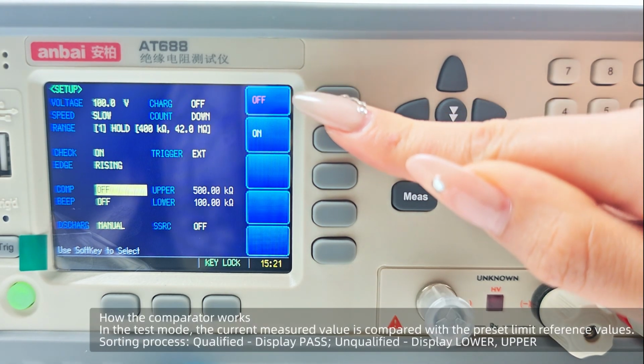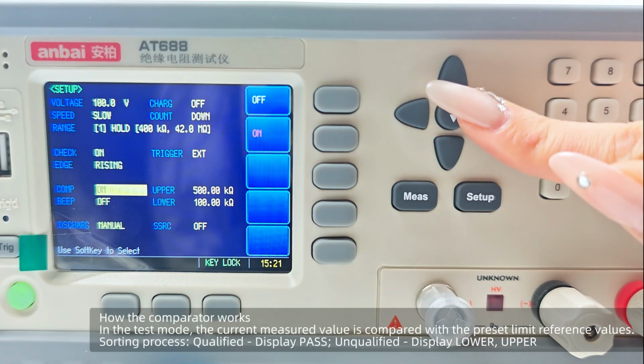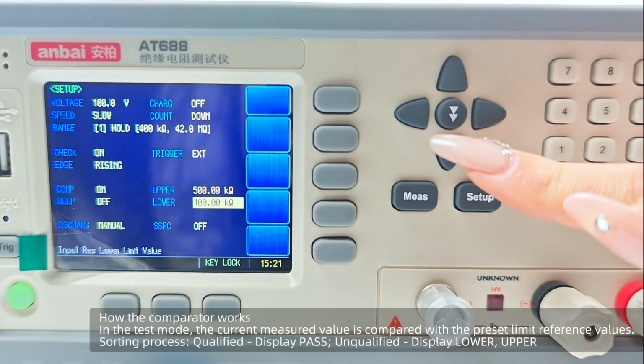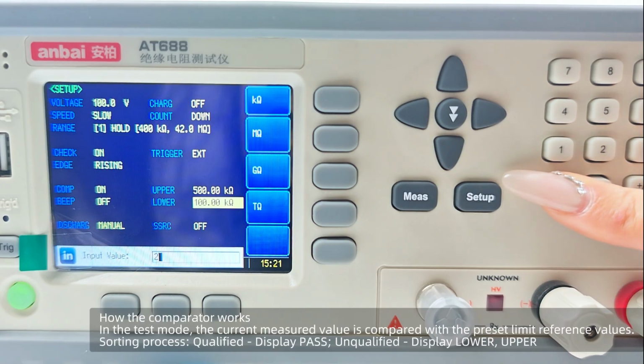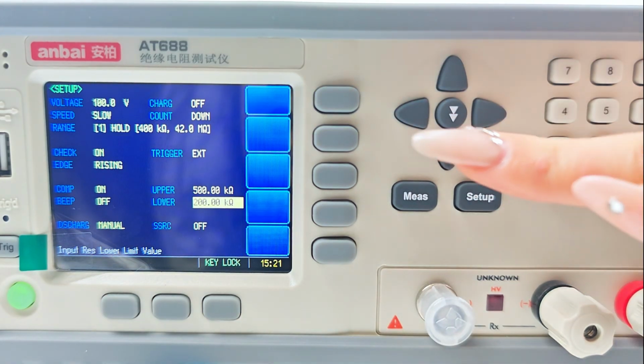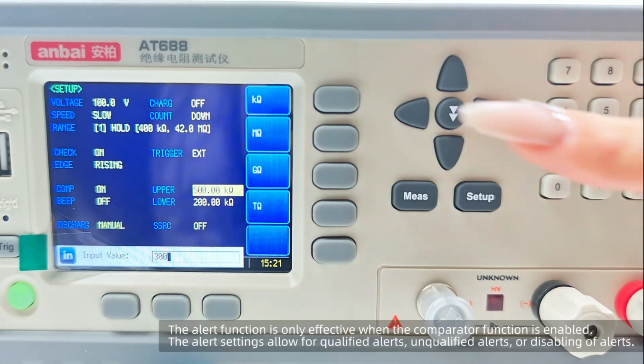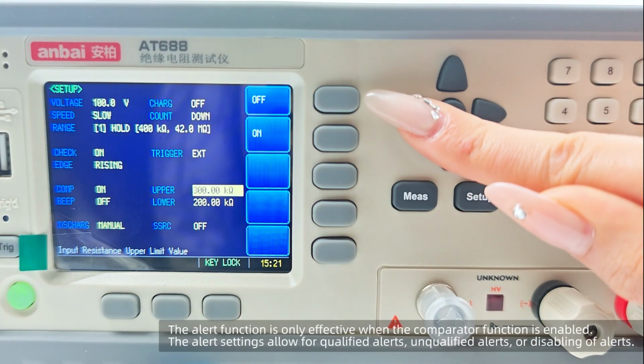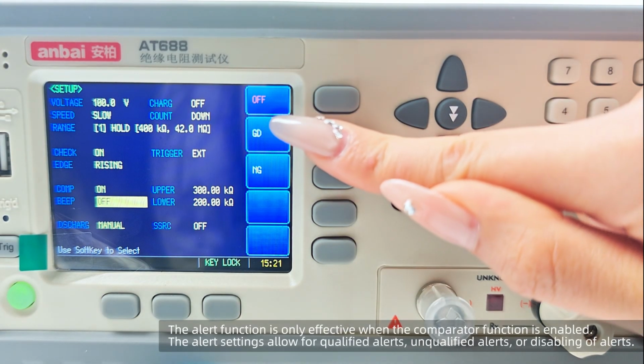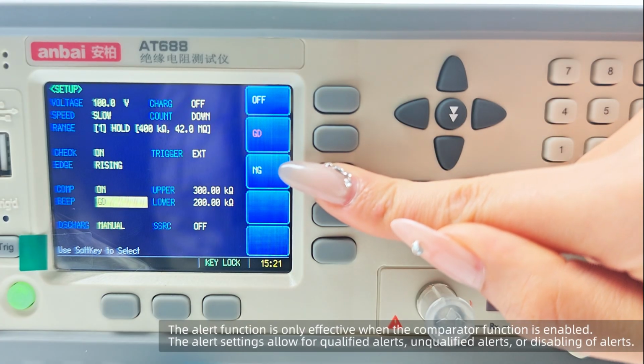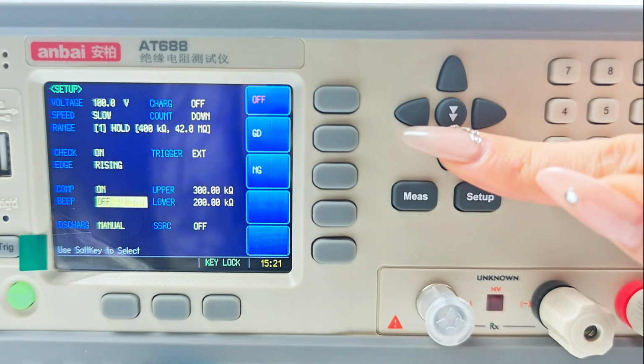The instrument can compare the measured resistance values. The reference values for comparison are input within the upper and lower limits. The upper limit can be disabled. The alarm function is only effective when the comparator function is enabled. The alarm settings allow for qualified alarm, unqualified alarm, or disabling of the alarm.